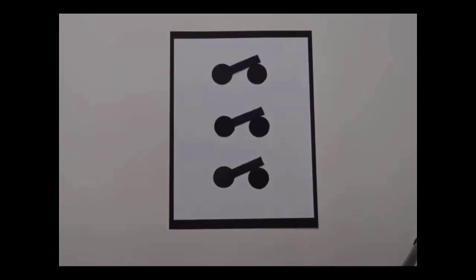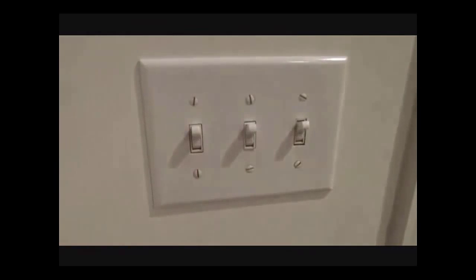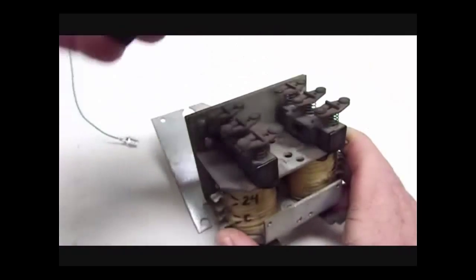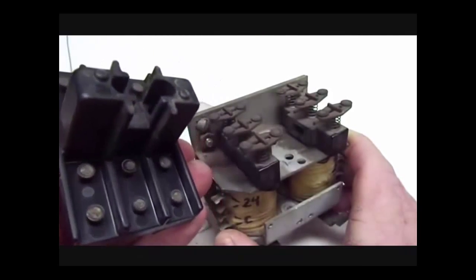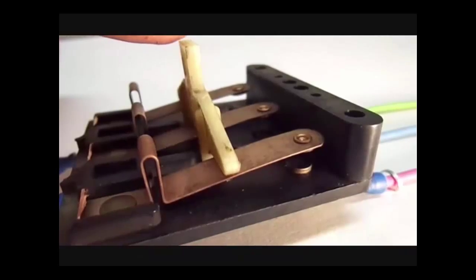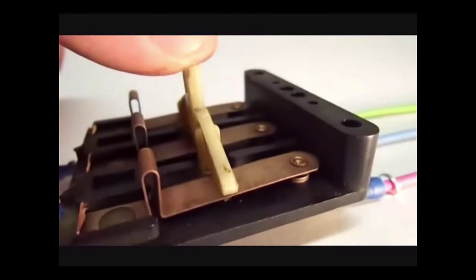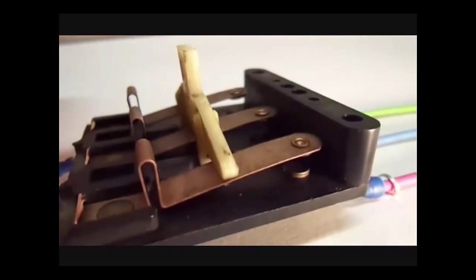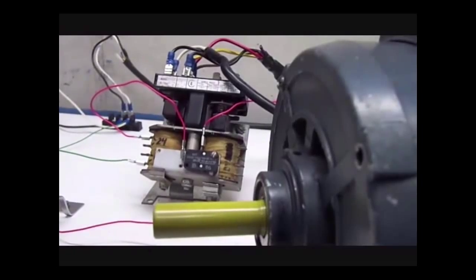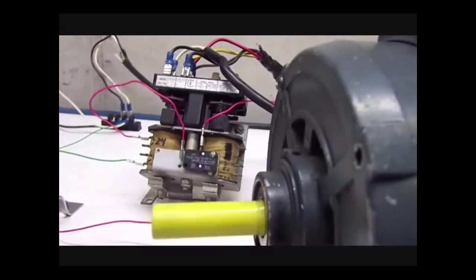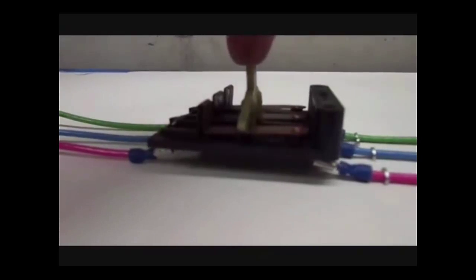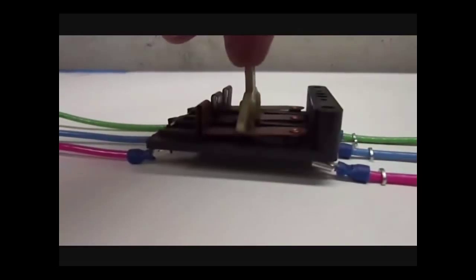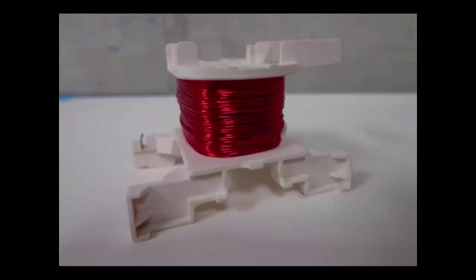This one has 3 poles. It's like having 3 separate switches that are all activated by that 24-volt coil. These poles are all independent of each other, so you could use them for 3 separate circuits with 3 totally different voltages. But most of the time, they're all used together to run a single motor. And any voltage you send through the main contacts is going to be isolated from the coil, so you don't have to worry about the high voltage mixing with the low voltage circuit.